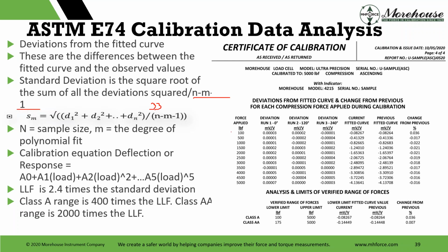Our points here, we took 33 points because some people only take 10. That's not good because how low can you use your instrument? You cannot use it below 400 times the lower limit factor or the first non-zero test point. So if someone starts at 500, the best they can do is use this device from 500 to 5,000. Morehouse, we took a 100, so the best they can do is use it from 100. In practice, they could have used it from like 33 based on this data.